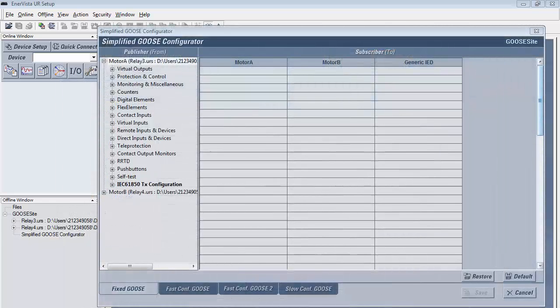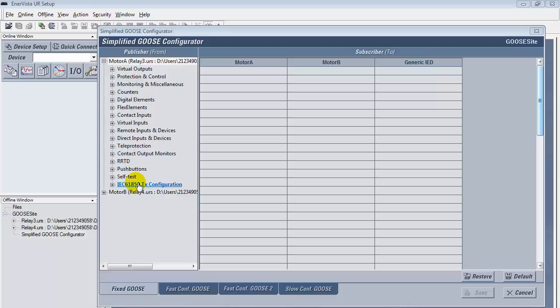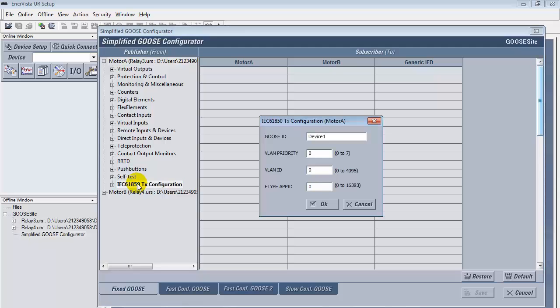Next, in the fixed GOOSE tab, open the IEC 61850 tab at the bottom of the list. We must now rename the GOOSE ID and select values for VLAN Priority, VLAN ID, and E-Type App ID. This must be done for both relays.